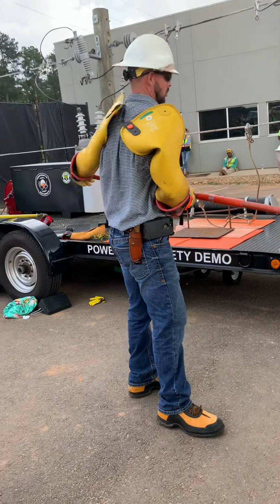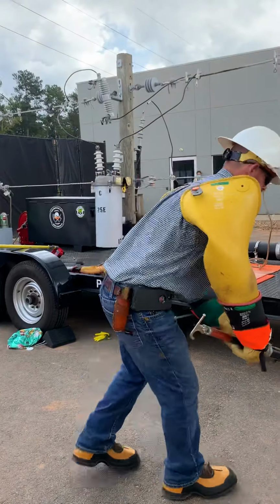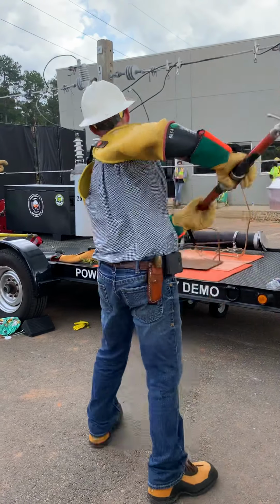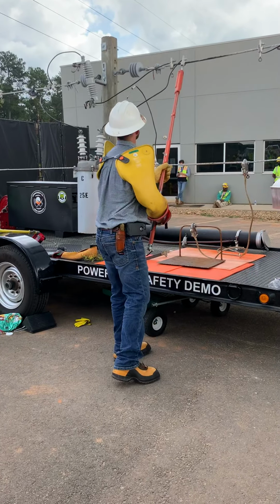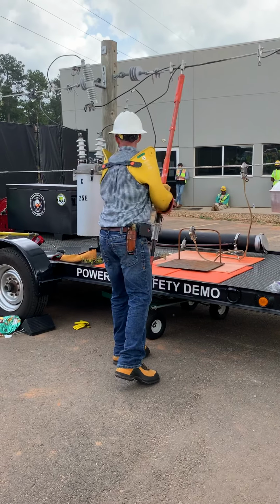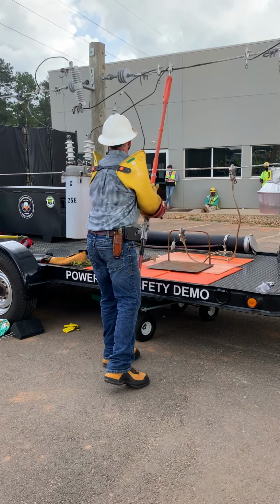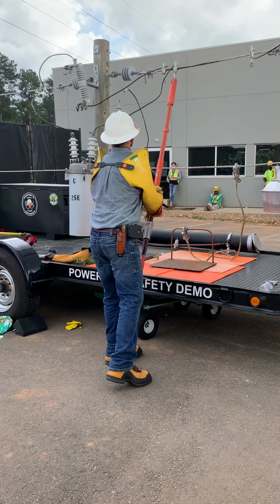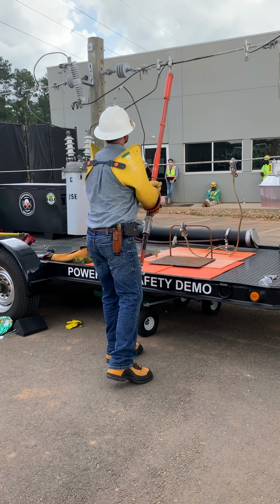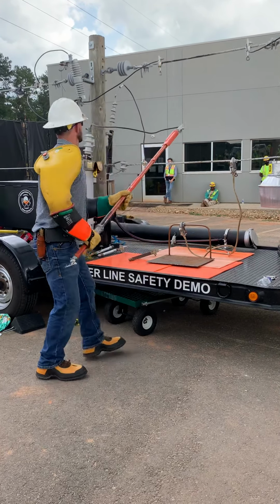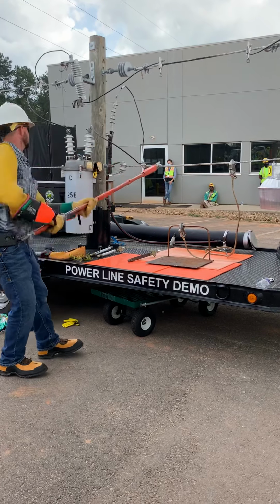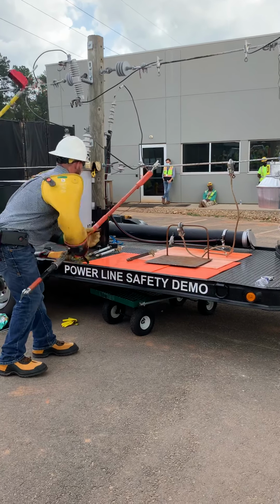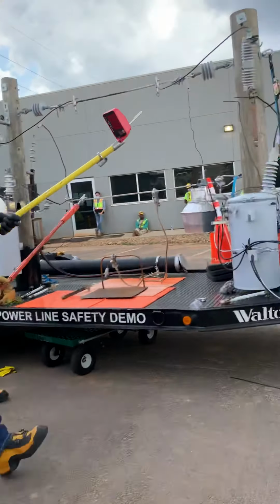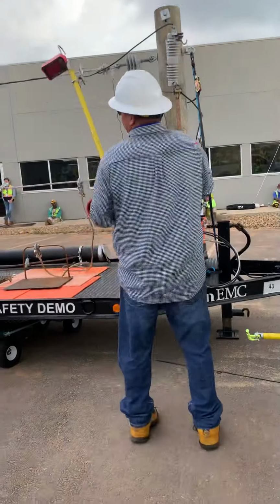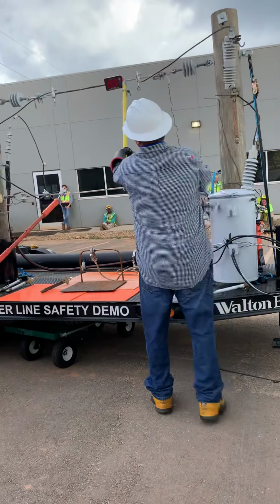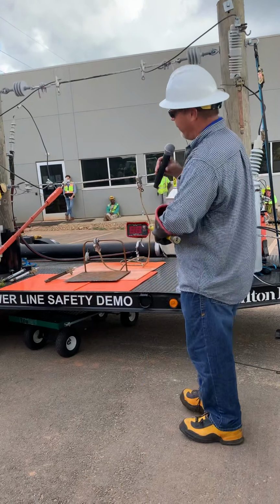So what we would do, we would get calls down the line. We come out, we ride by here, this device is open. We know we got trouble that way. So we can't do anything barehanded until we do what we call tag, test, and ground. That would be getting us an air gap. Right here, without that barrel in, that's an air gap. On the other side is an air gap. Then we take a meter like this and check for voltage. No voltage, then we can apply our grounds.